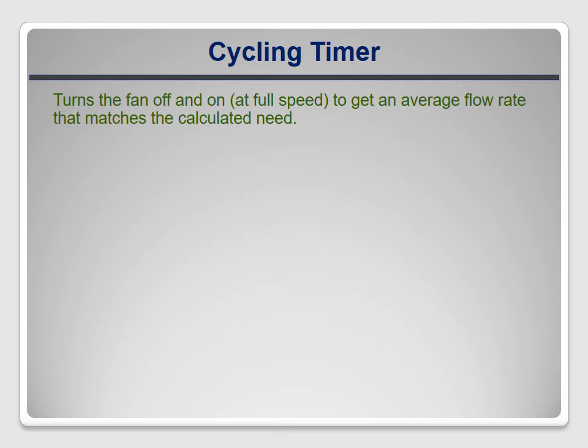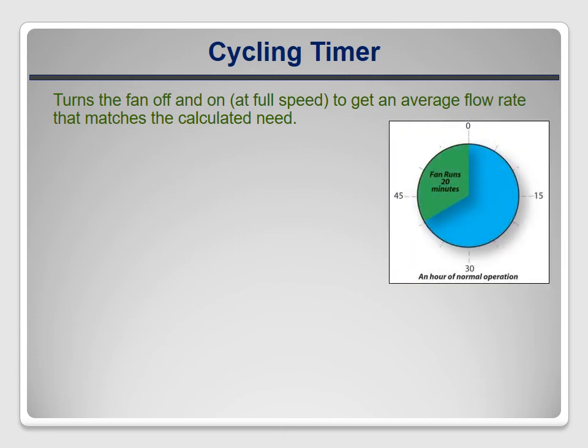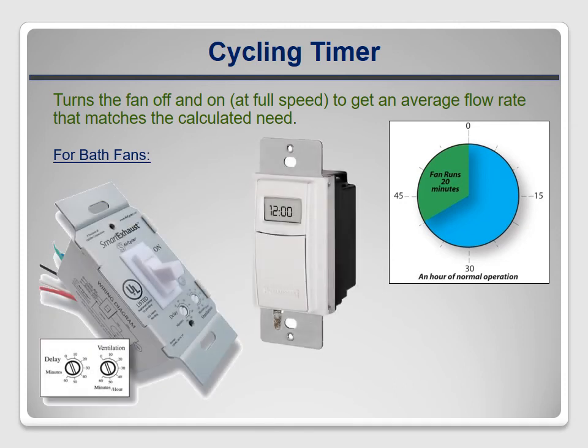All of the other external controllers I've seen run the fan at full speed, but cycle it off and on, usually for an adjustable number of minutes every hour. If you need 30 CFM but the fan runs at 90, then it only needs to run a third of the time, or 20 minutes every hour. Here are two examples. The smart exhaust is nice because the settings consist of only two dials — one is for the minutes per hour of runtime, and the other is for the high-speed runtime when the bathroom is used. I installed this one in my last house, and it worked great. The other one allows day-by-day programming and is often available at big-box home stores, but like programmable thermostats, it can be challenging for occupants to use.